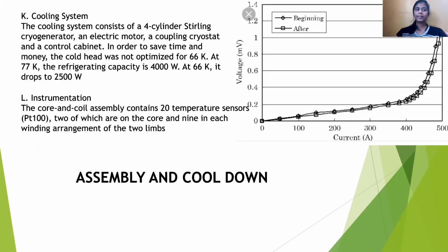Cooling systems. The cooling system consists of a 4-cylinder Stirling cryogenerator, an electric motor, a coupling cryostat, and a control cabinet. In order to save time and money, the cold head was not optimized for 66 K. At 77 K, the refrigerating capacity is 4000 watts. At 66 K, it drops to 2500 watts.